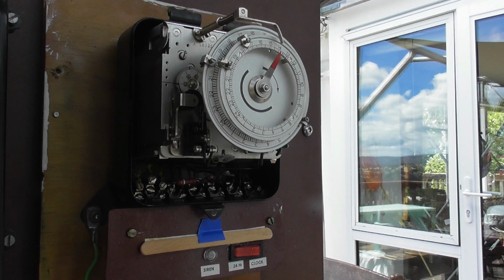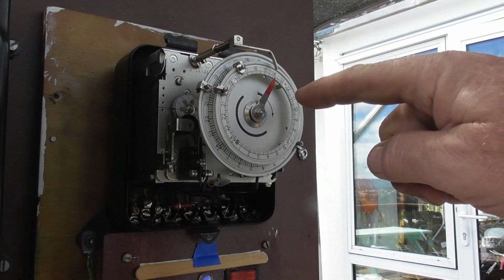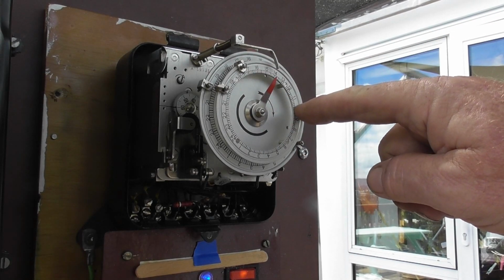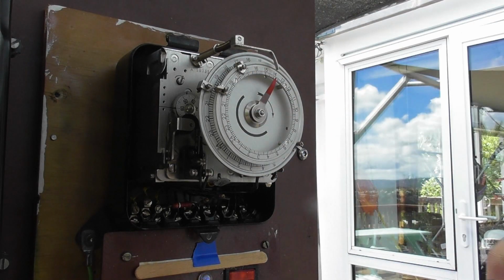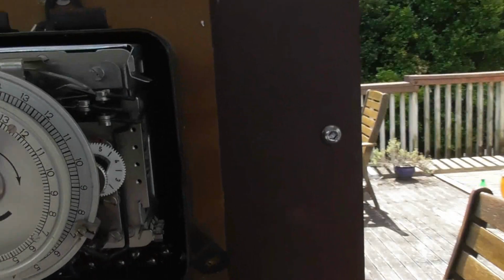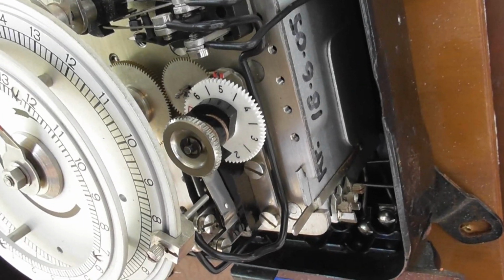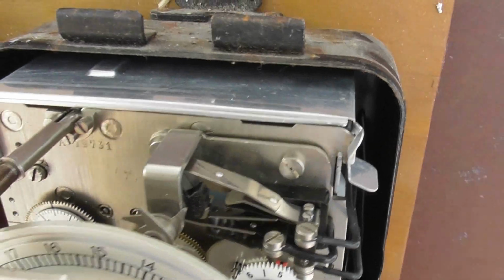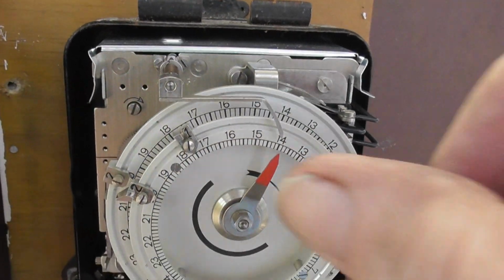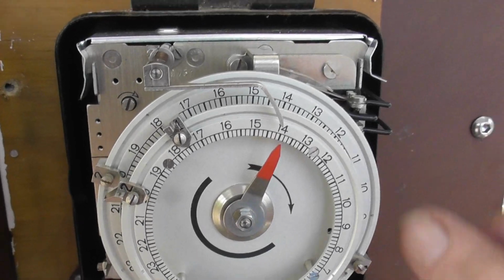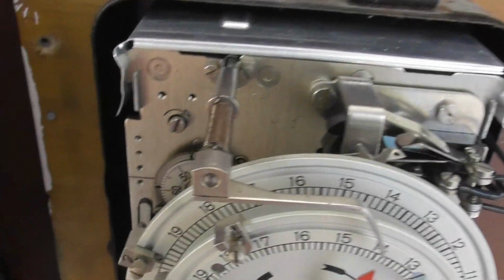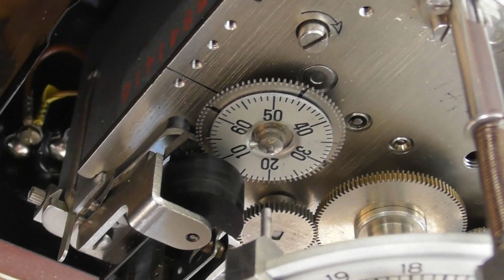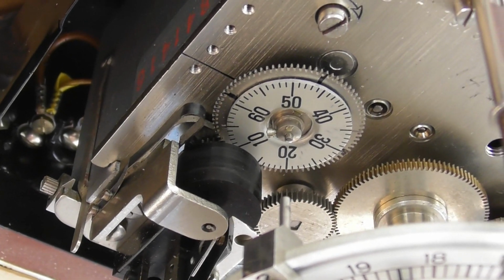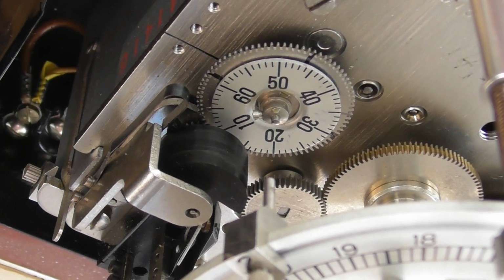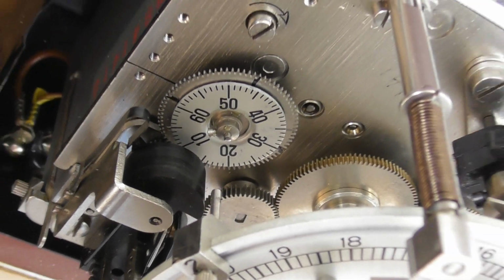It's actually quite a nicely made clock, so it's got a couple of dials. You've got an inner circle you can set up the times. We register 1, register 2 is the outer dial on the clock itself. It's got a week program in there as well, so you've got a week dial in there for selective. You've got a top contact and a bottom contact which goes via this lever here. There's a 15 minute contact as well, that's for the maximum demand pointer. It's not used in this kit. Oh, it just goes to a click there, and coupling, and then, yeah.